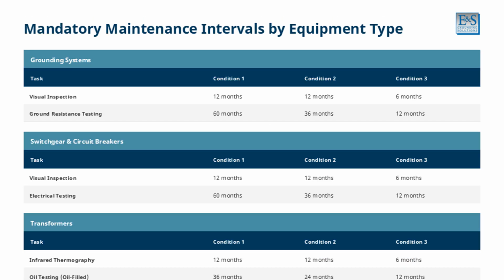NFPA 70B Table 9.2.2 specifies mandatory maintenance intervals by equipment type and condition. For grounding systems, visual inspection requires 12 months for conditions 1 and 2 and 6 months for condition 3. Ground resistance testing requires 60 months for condition 1, 36 months for condition 2, and 12 months for condition 3.